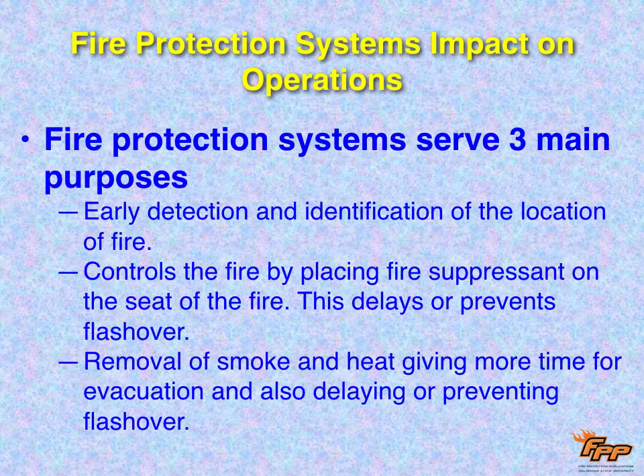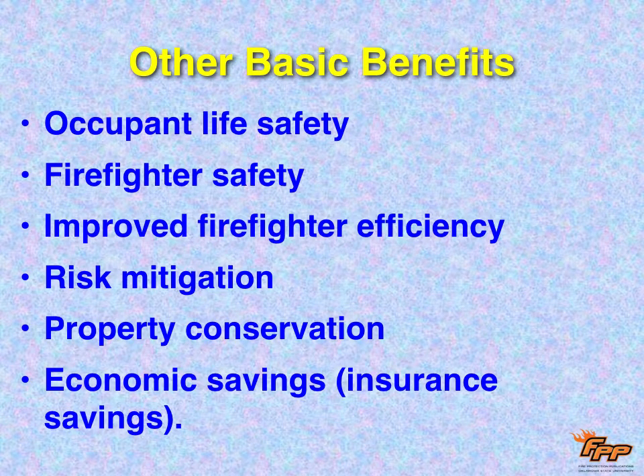So fire protection systems serve three main purposes, and we kind of referred to this already. Early detection and identification of the location of the fire. Controls the fire by putting suppressant on the seat of the fire. Delays flashover. And thirdly, removes smoke and heat, giving more time for people to evacuate and also to delay or prevent flashover. There are other benefits, of course: occupant life safety, firefighter safety, improved firefighting efficiency, and the money. It mitigates risk, therefore conserving property. And of course, the insurance companies are happy with that because it saves them money.